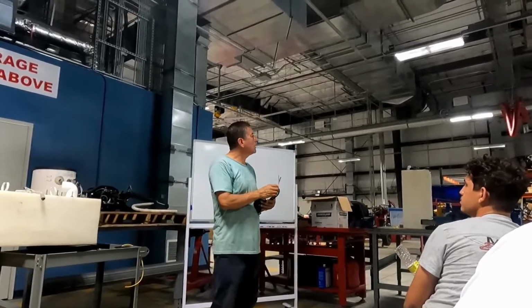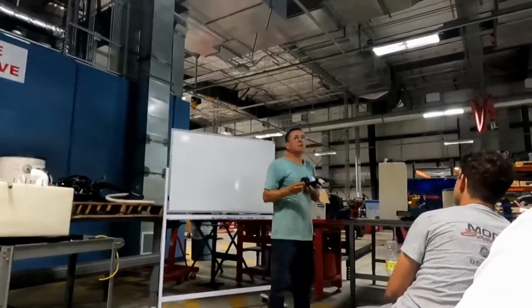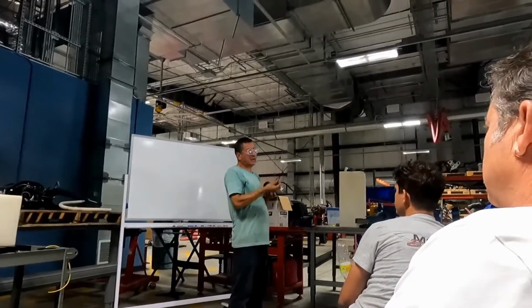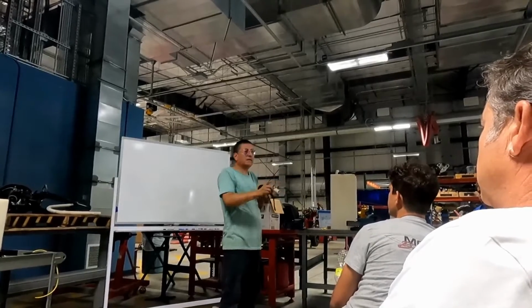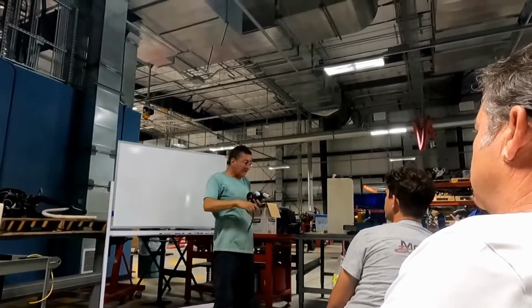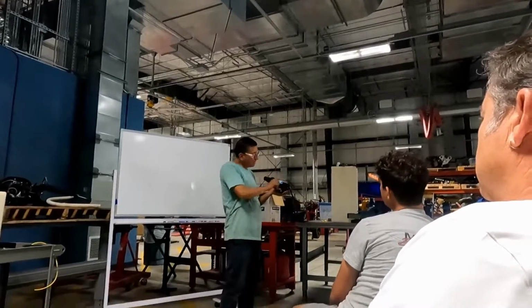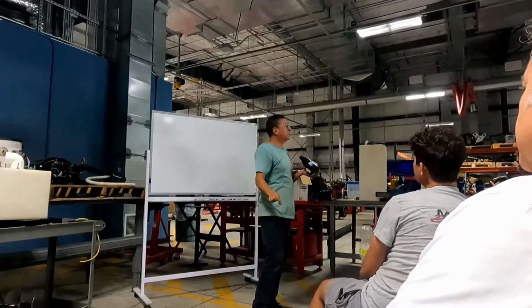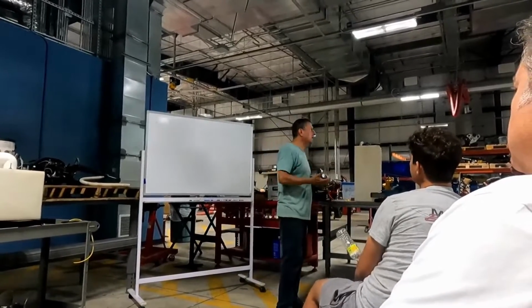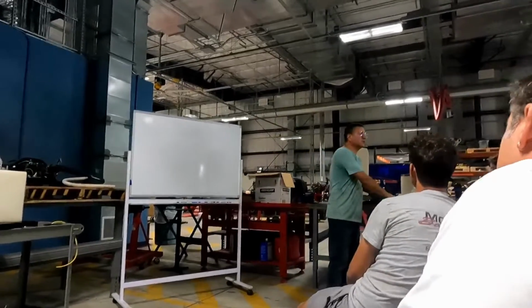One other color, green. Look at this. This is a DC pump. You have black and red, or black and orange in this particular case, or yellow instead of black. That's for the power. And additionally, because this is metallic, you need another cable from the case of this green color into the bonding. The people say, no, the DC doesn't need bonding. Okay, don't bond them, and this is the consequence.